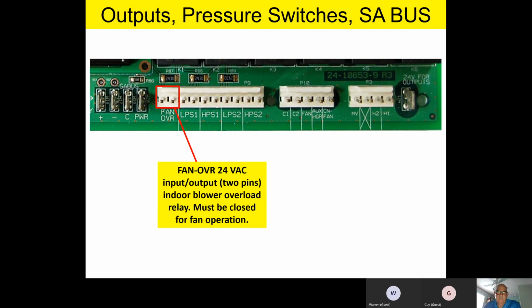And if you've got a replacement motor that doesn't have that, you'll sit here and scratch your head all day long. Why isn't the fan running? What's going on? Well, that fan overload has got to be closed electrically on the board in order for it to output FAN on the pin to bring the contactor on. So it'll drive you crazy unless you know that. Good question. Any other good questions or comments?